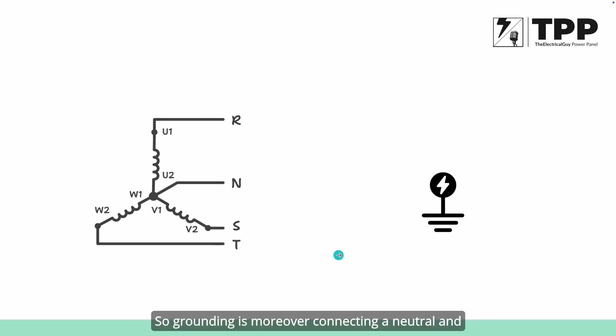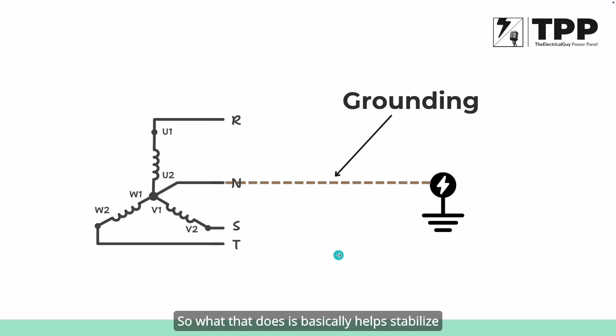Grounding, on the other hand, is different—it's more about connecting a neutral and earth together. This helps stabilize the voltage profiles along the system. At the same time, it ensures that any fault condition occurring in the system has a low impedance return path to the source.